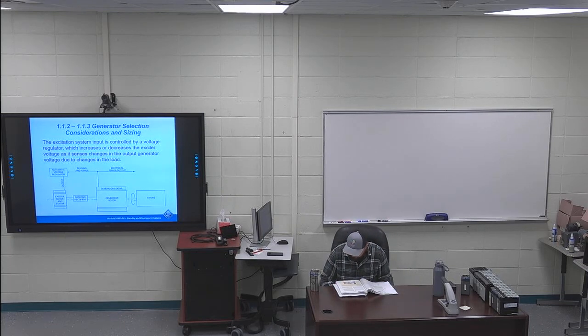In the places that I've worked, you can see on page 5 those big exhaust vents, and that is exhausting. You couldn't have the carbon monoxide inside that room. They say the fans blow stuff around, but really it's the carbon monoxide and stuff off of the diesel fumes being exhausted out of those rooms. That is a super clean generator room. Ones I've been a part of at Goodyear and Nucor did not look like that. They weren't bad, but that is a clean room compared to where I've been for emergency backup power.